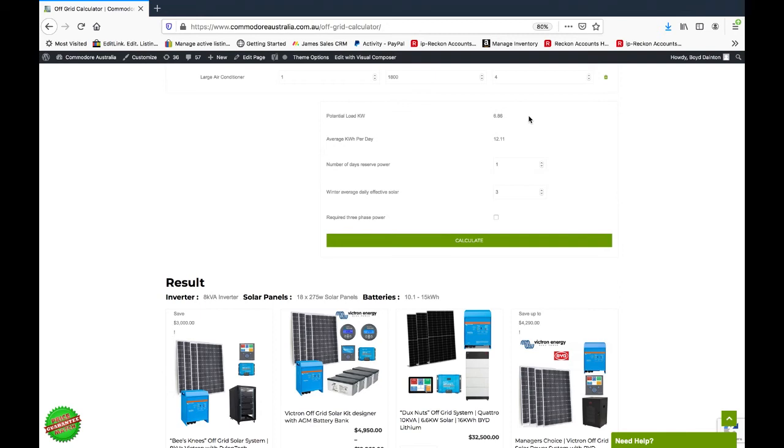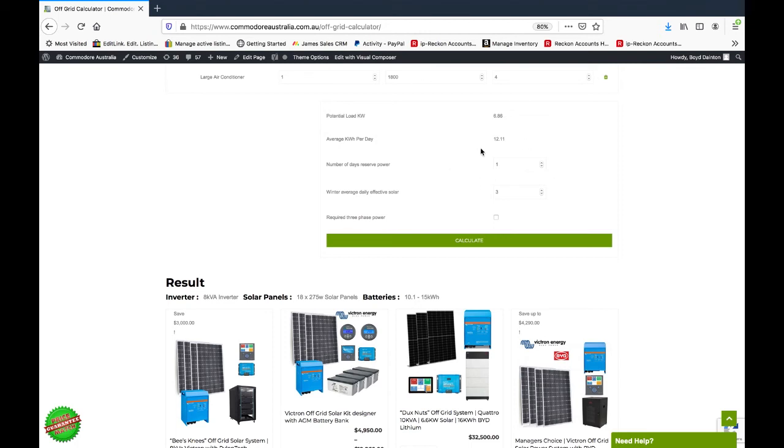We've then got our solar panels. We're working on basically your average kilowatt hours per day divided by three, and that will match up the solar panels accordingly. And the batteries—the battery storage is your average kilowatt hours per day.